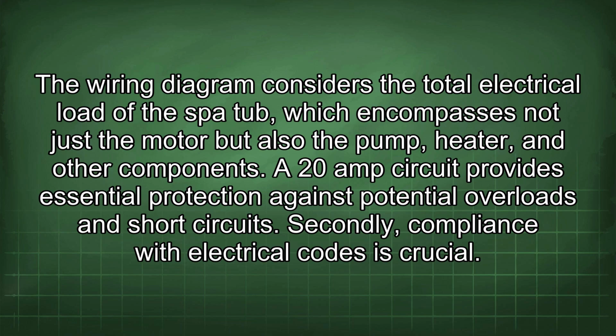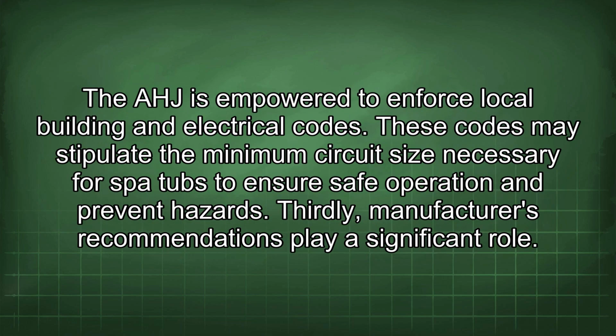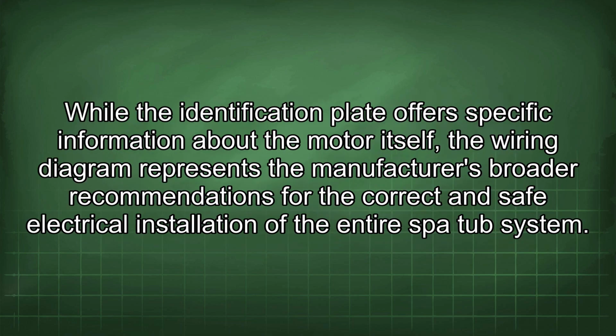Secondly, compliance with electrical codes is crucial. The AHJ is empowered to enforce local building and electrical codes. These codes may stipulate the minimum circuit size necessary for spa tubs to ensure safe operation and prevent hazards. Thirdly, manufacturers' recommendations play a significant role. While the identification plate offers specific information about the motor itself, the wiring diagram represents the manufacturer's broader recommendations for the correct and safe electrical installation of the entire spa tub system.